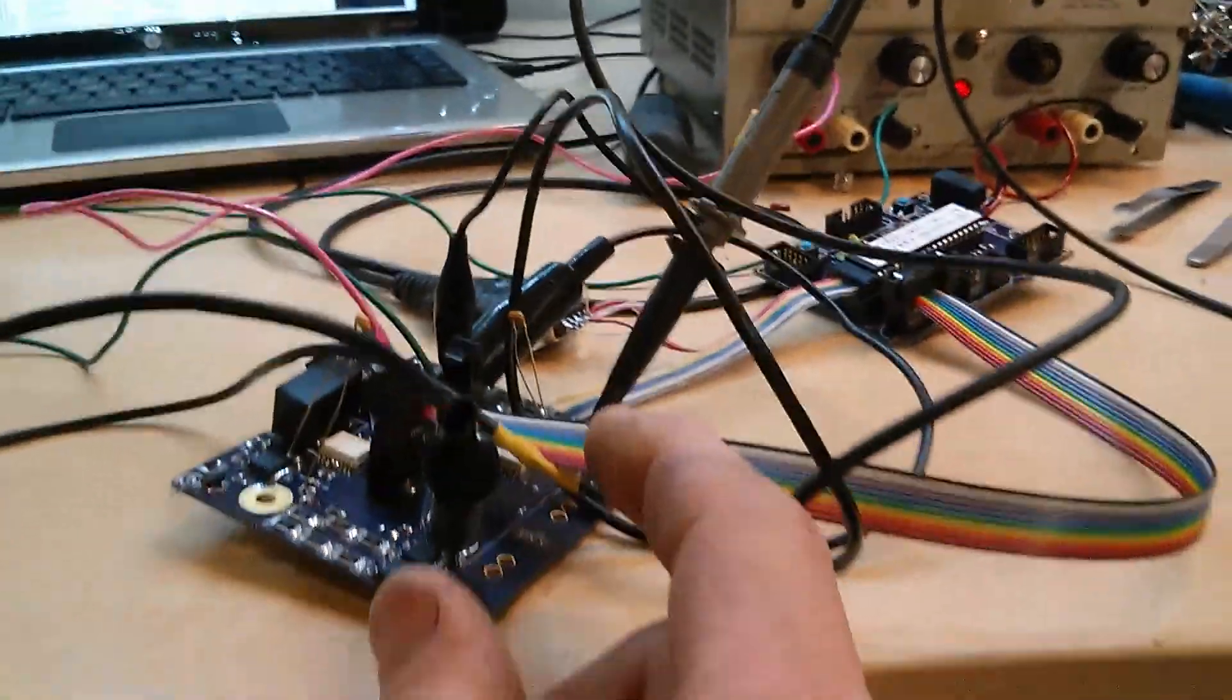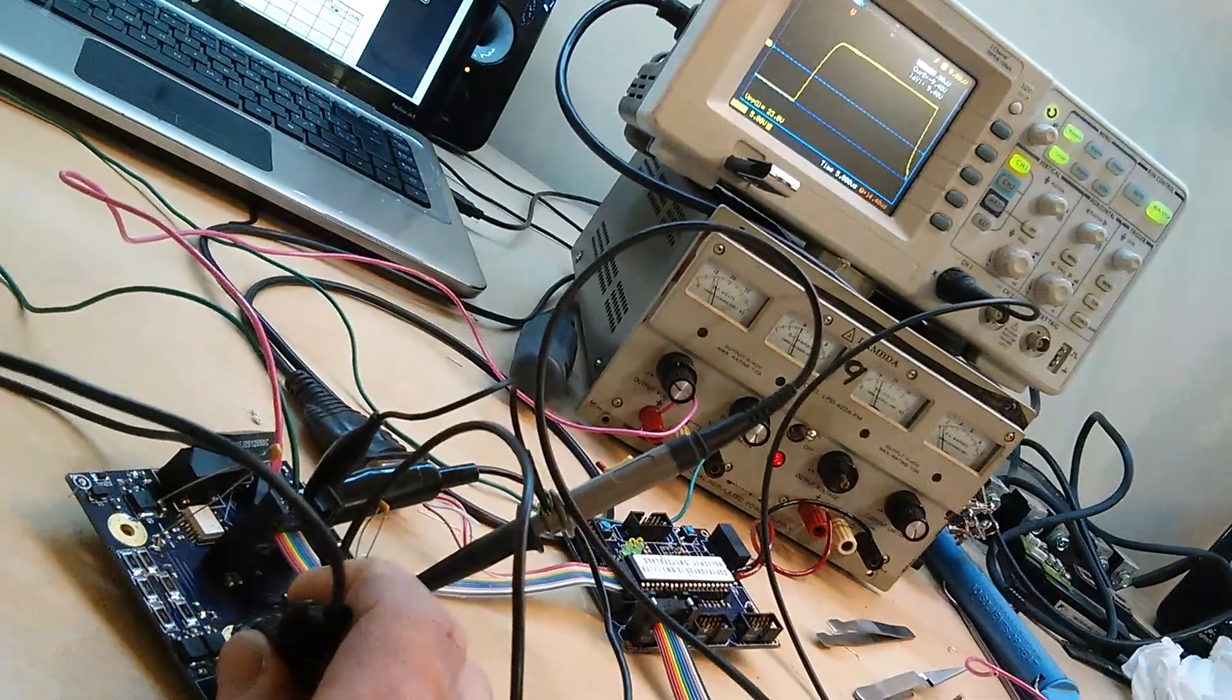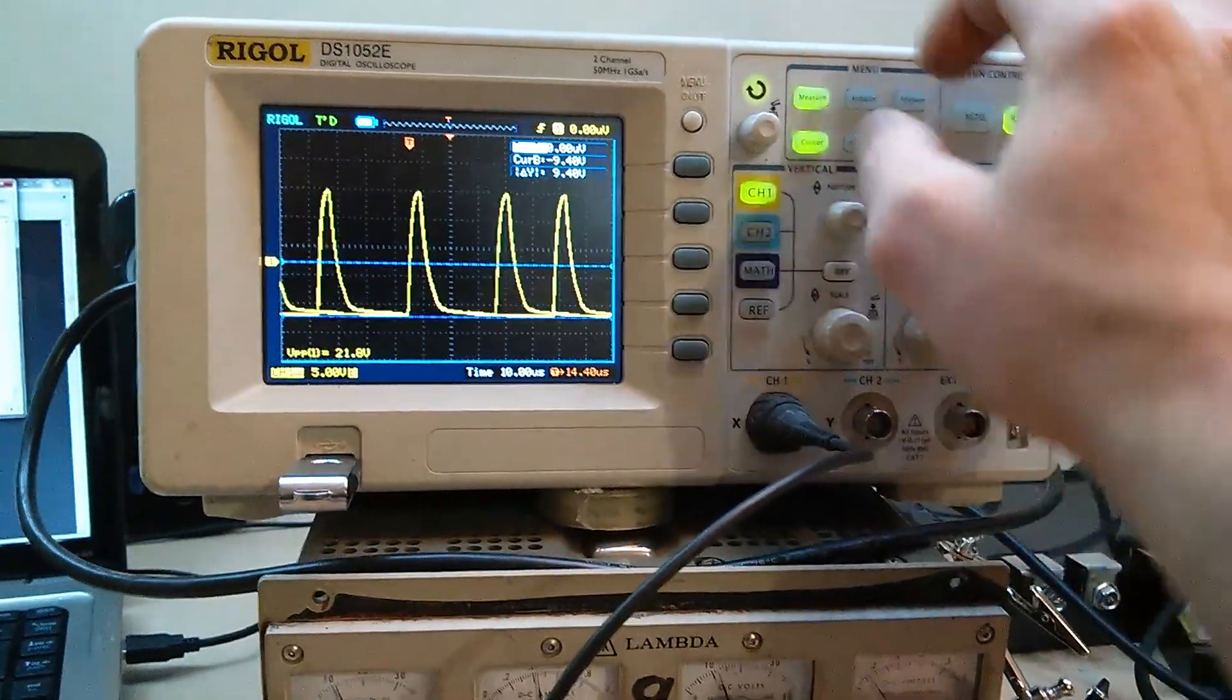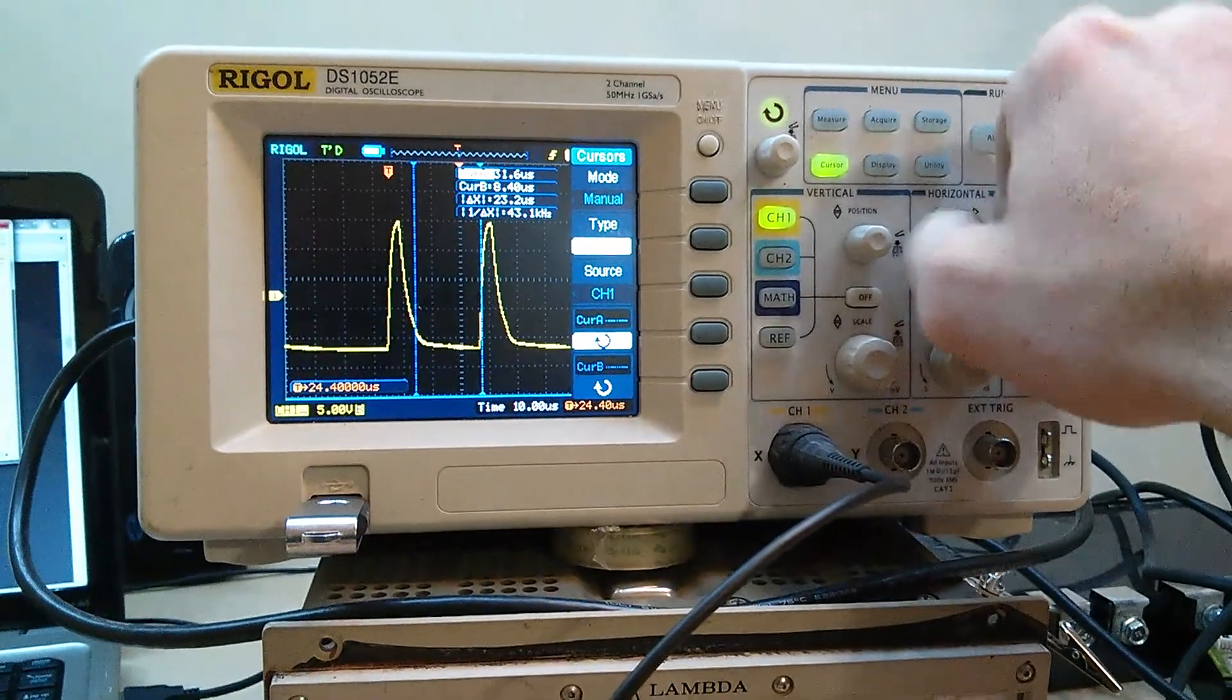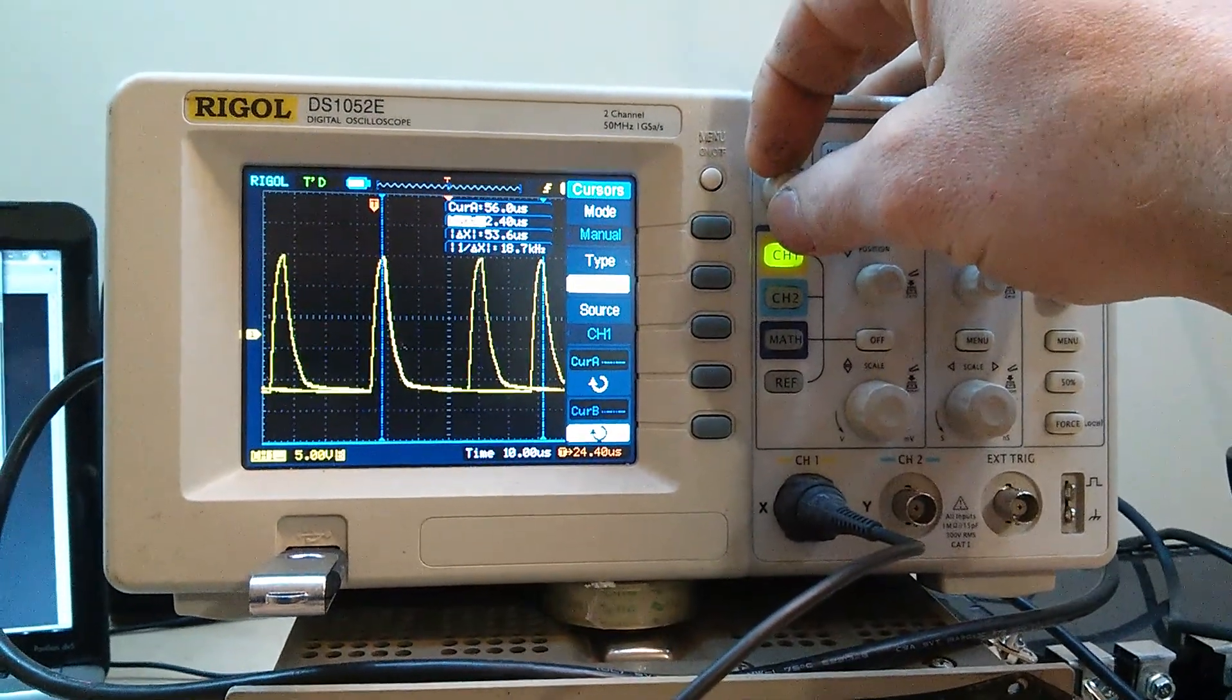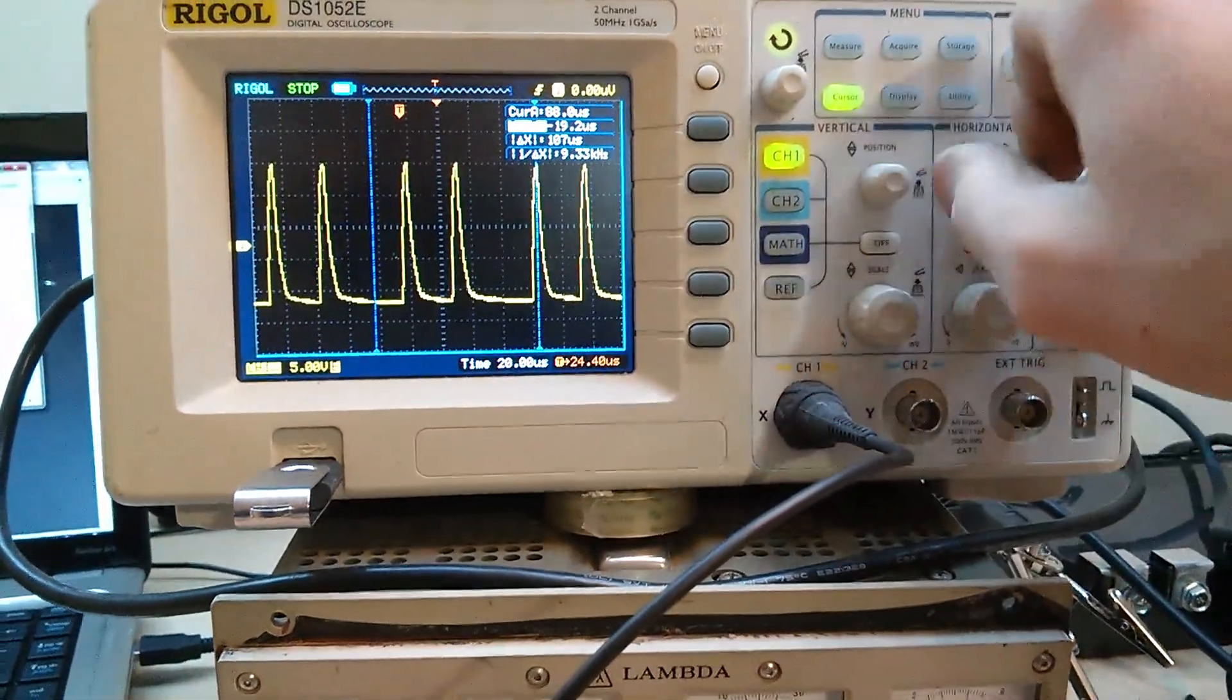Nonetheless, you can see it right there. Now I'm going to unhook this wire right here, which basically, I'm going to turn the camera on an angle. This will actually shut off or activate the desaturation detection. And you can see there it is. And what it's doing right now is it's actually trying to turn back on. Here it is. Let's do the cursor here. Go to YX. Slide this across. This will show 18 kilohertz. I don't quite have it right. Let's put a freeze on that.